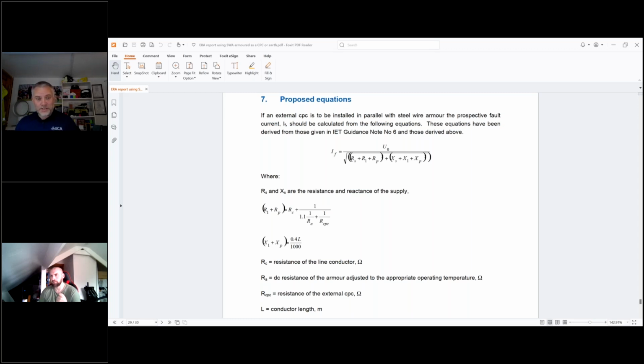On the back end of that, there's a British standard which is all about designing cables with separate CPC and protective devices. And this equation here that I'm showing you made its way into a UK annex. So when we're asked, does this affect Europe? This is a UK specific annex in a document, and it's in the PD CLC TR, which is technical report 50480. So a few people online have already mentioned this, and that's the report it came into.